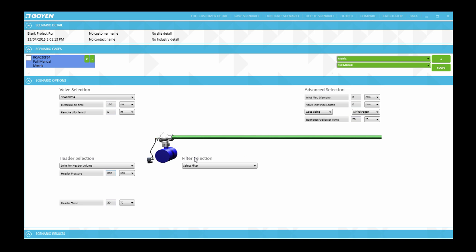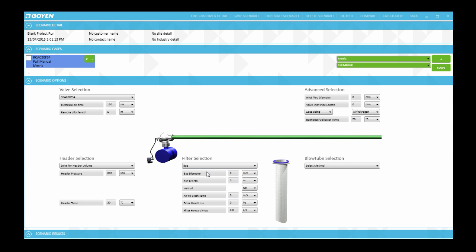In this example we will use typical values for a coal-fired boiler example. The first parameter to specify is the filter bag diameter. Once we go to the select filter drop down menu and we select bag, the bag diameter would be 150 which is 6 inches. Other common sizes include 4 inches 100 millimeters or 5 inches 125 millimeters.